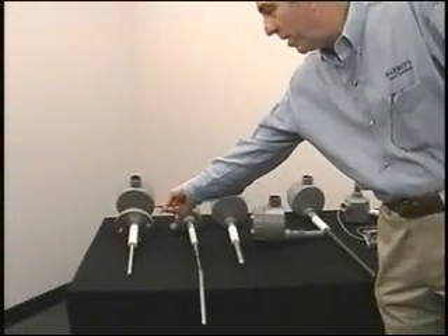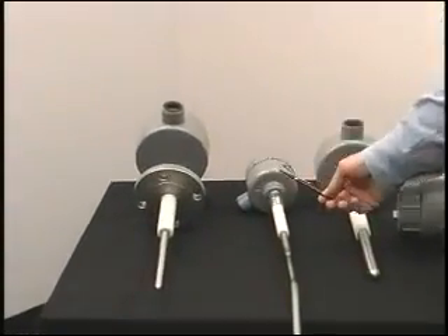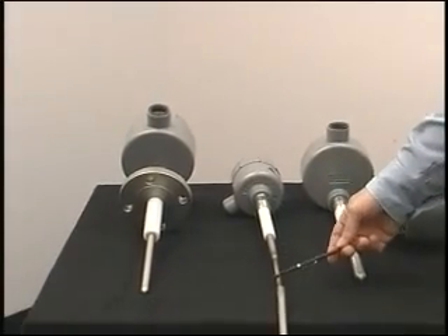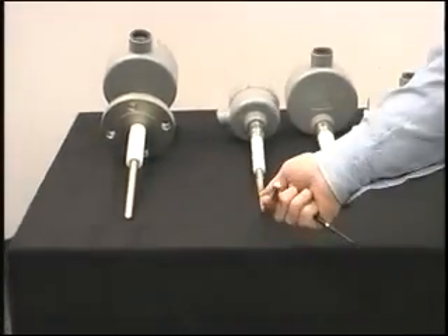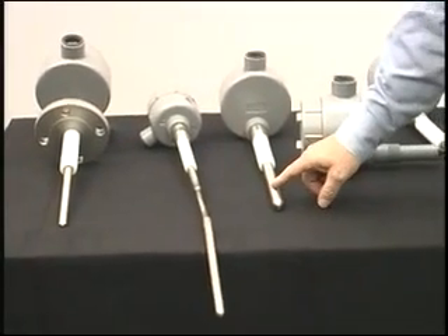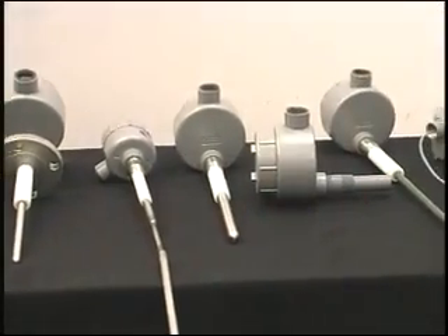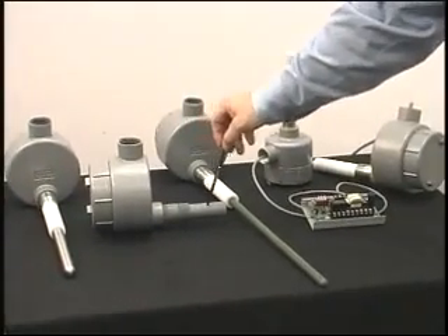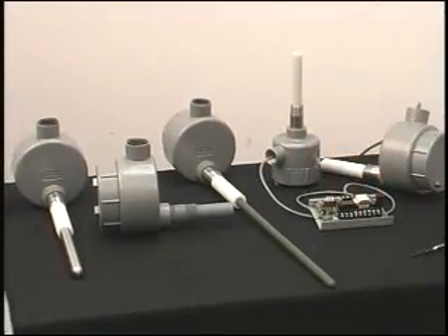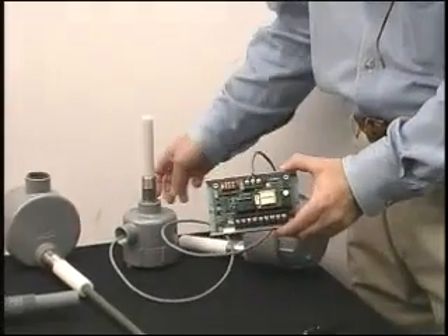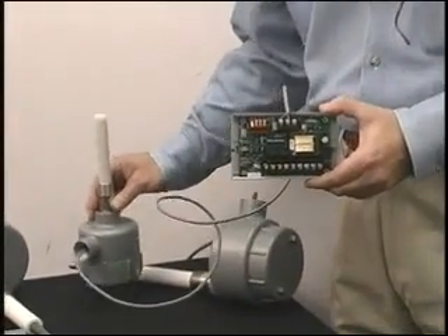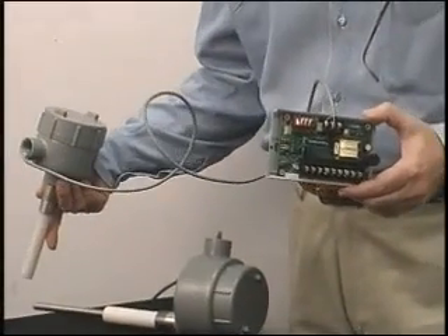What I just demonstrated for you was the LS7000. If you take away the time delay and the test switch, we have the LS6000, which is a lower cost alternative. It's shown over here with a welded flange, which is an optional process connection. We also have probes available with flexible wire ropes, which can go up to 150 feet. 3/4 inch diameter probes for very rugged applications. This is a PVC probe and process connection, a Halar coated probe, and finally our LS8000 is a remote mounted level switch where you can put the electronics up to 1 mile away from the probe on a twisted shielded pair.